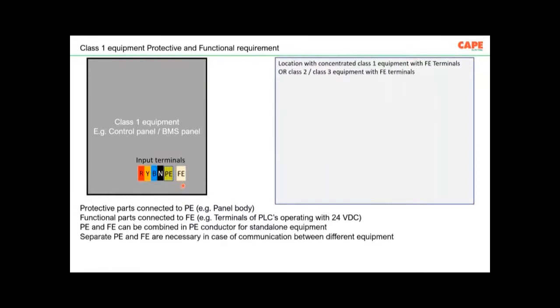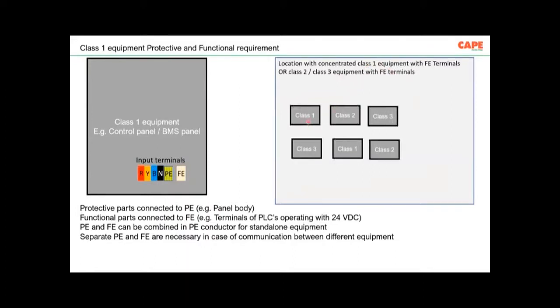Now, let us see how you make earthing in a control room, for example. A location where concentrated class 1 equipment with FE terminals, class 2 and class 3 equipment with FE terminals, means functional earthing terminals. How to make earthing? You have some class 1, class 2, class 3 equipment. The first one is safety. All the class 1 equipment which is having a PE terminal must be connected to the MET, means main earthing terminal or equipotential bonding conductor. So this dotted line, green and yellow, is called a protective earthing, which is necessary for class 1 equipment.